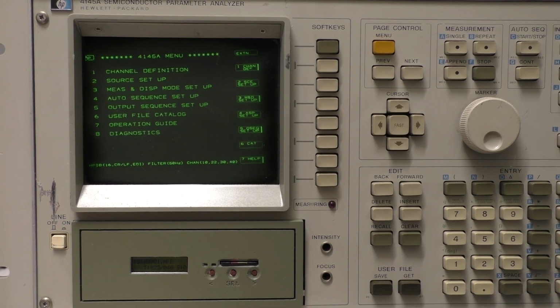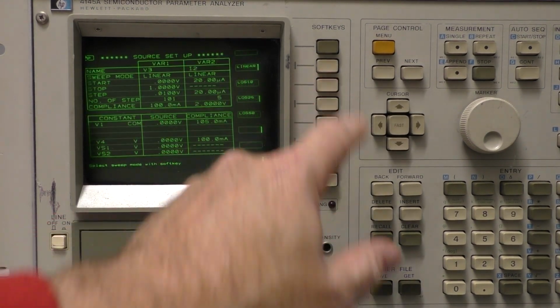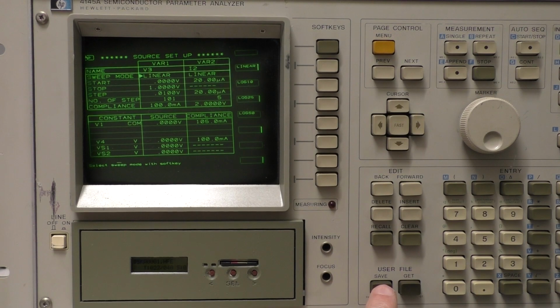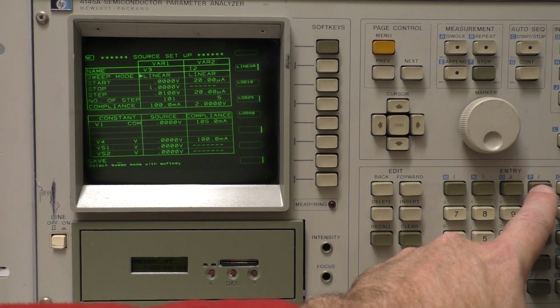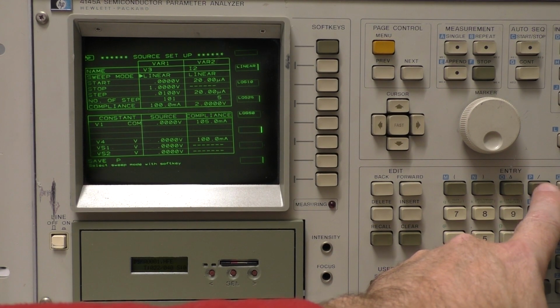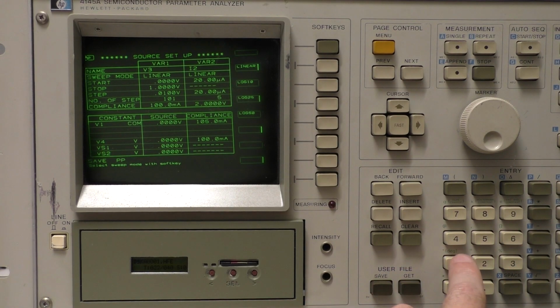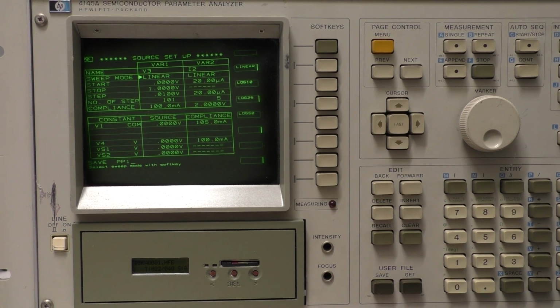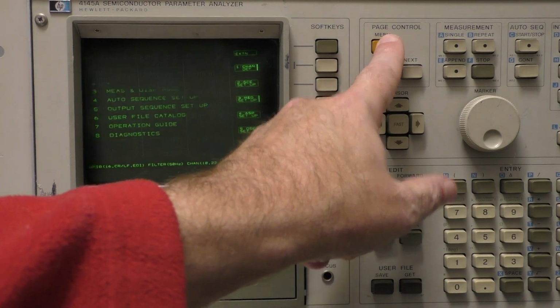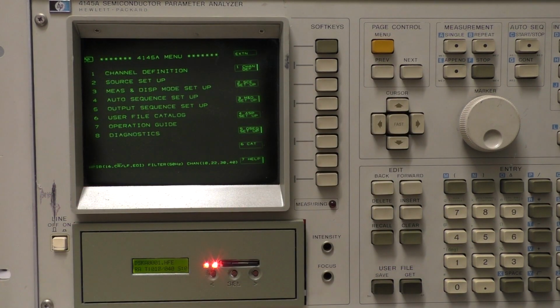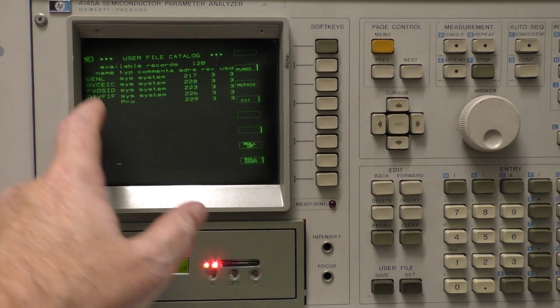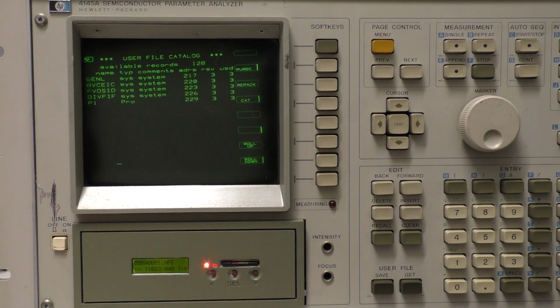Let's now ensure we can write to the SD card. From the main menu, go to Source Setup. Press Save. Now enter a P to set the file type as a program. Now enter a file name, in our case we enter P1. Now hit Execute. This should save the measurement program in the user file P1. Note the disk write LED flickering. Go back to the main menu. Press User Catalog. We confirm the new program file stored on our SD card is present.